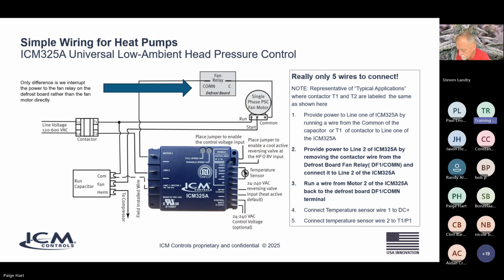Now we're going to make our own field installed wire, and we're going to go from motor 2 of the ICM back to that DF1 terminal on the fan relay. In this case, it's called common on the fan relay, but a lot of defrost boards might be labeled DF1, DF2, ODF1, but you're going to see a power leg. So that power leg has to be powered by our ICM control, so that when we are in cooling mode, we are modulating the voltage through that relay to the fan motor. Okay, all the other connections are exactly the same.